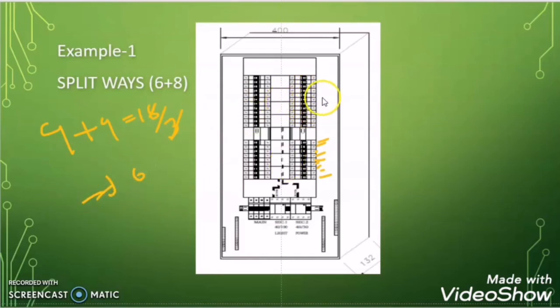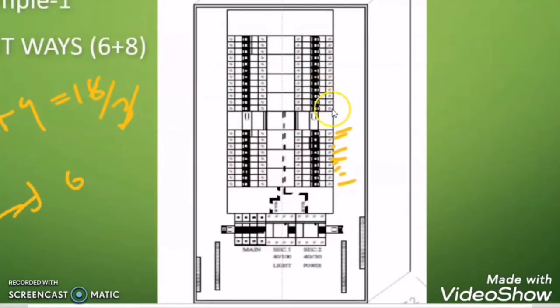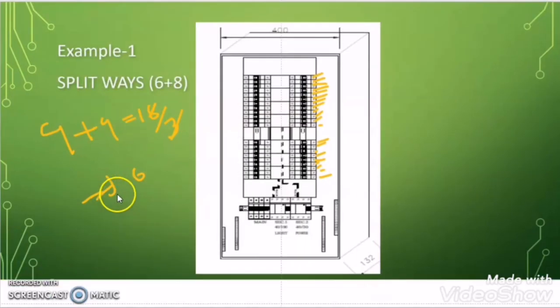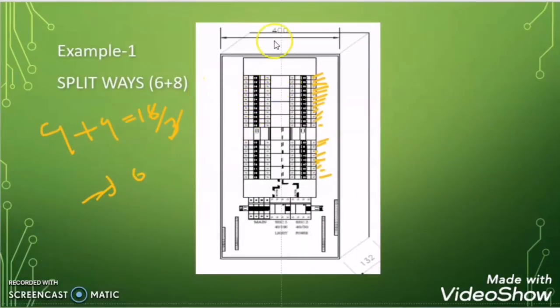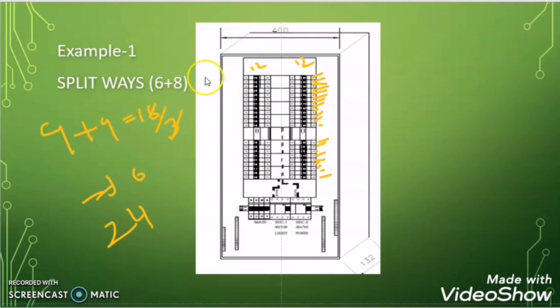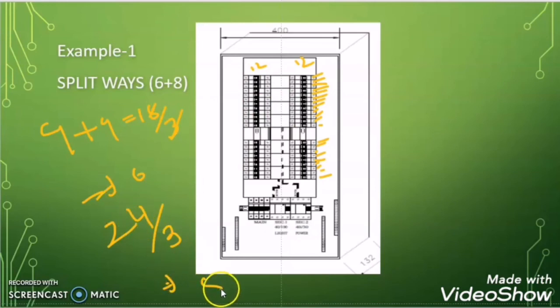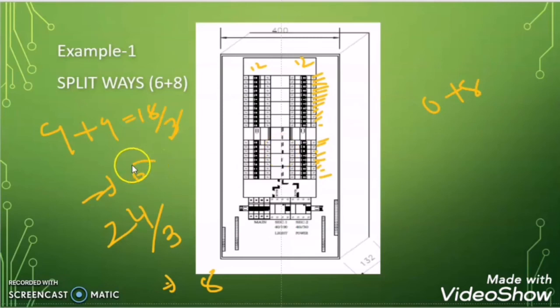Now counting the breakers in section 2 gives 12 plus 12, totaling 24 breakers. Dividing by 3 gives 8. So this final distribution board is a split way type of 6+8, because section 1 is 6 way and section 2 is 8 way.